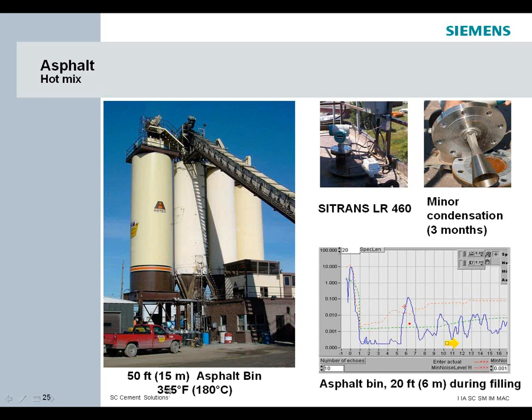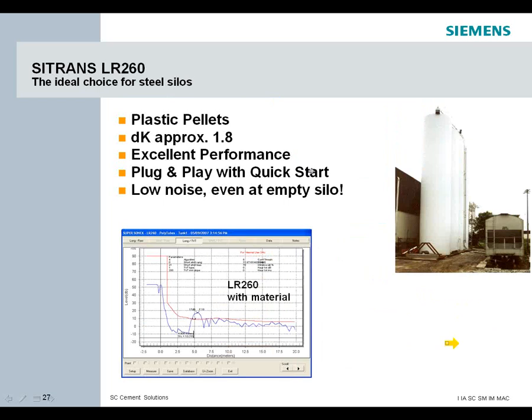Lime dust — let me mention a couple of things aside from applications. Siemens, formerly Milltronics, we're here in Grand Prairie, Texas. We support all the sales channel partners. Lessman is one of our key sales channel partners in the U.S. and we like to work through them and with them on applications and support. The radar devices are not limited to solids — we do liquids as well. You can see here these are plastic pellets. Plastic pellets can be difficult because they're very low dielectric and their reflectivity is not as strong as you'd get with water or cement. The LR-260 works quite well in these applications — these are about 40-foot tall bins at a molding facility.